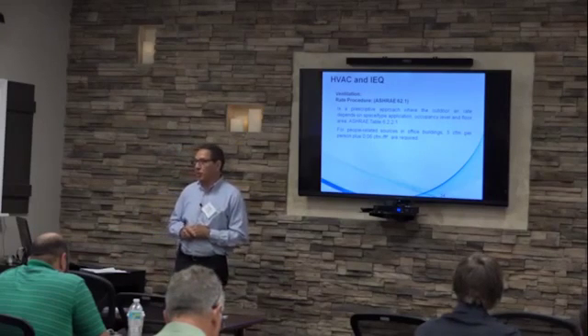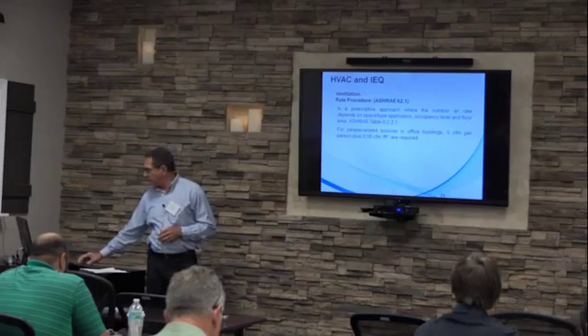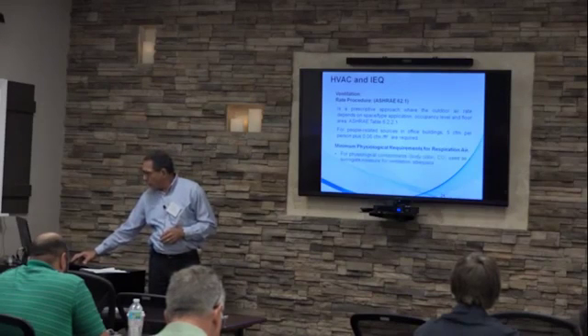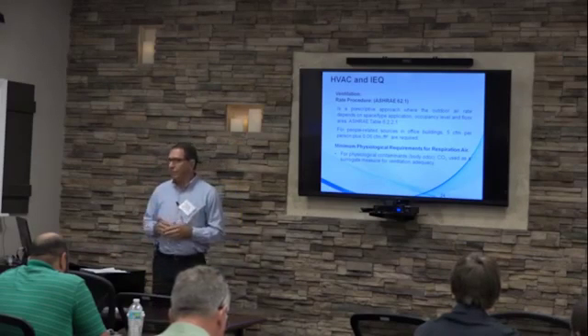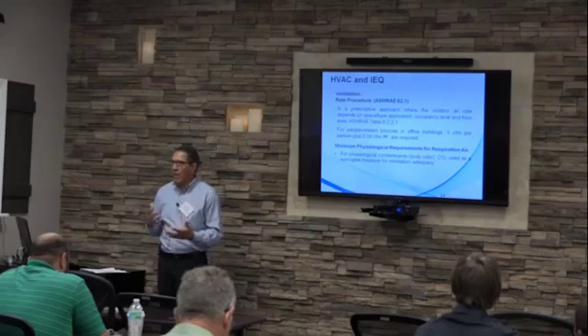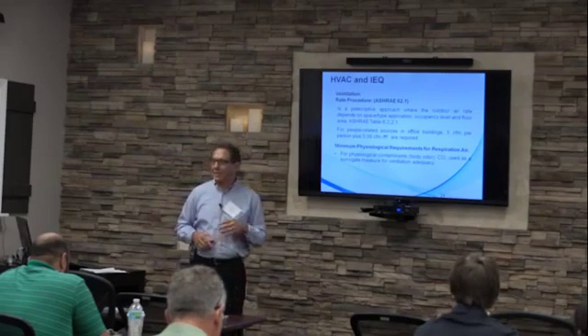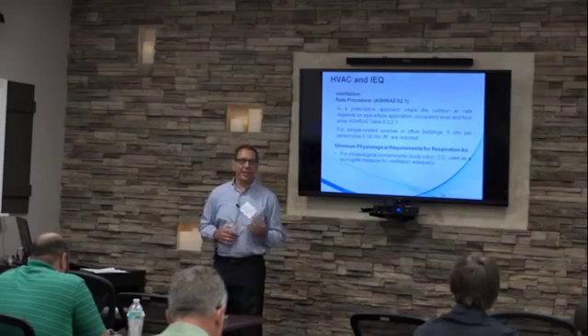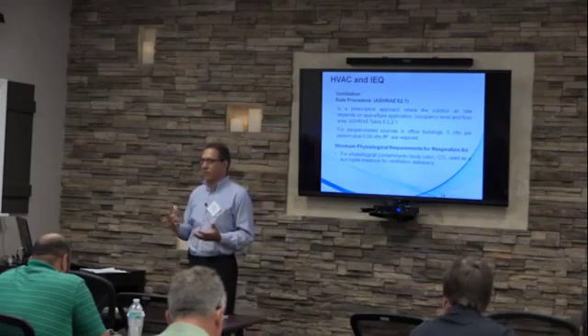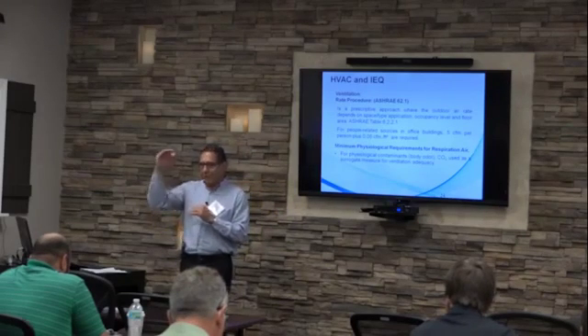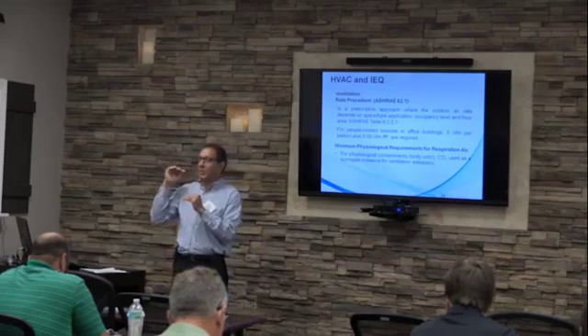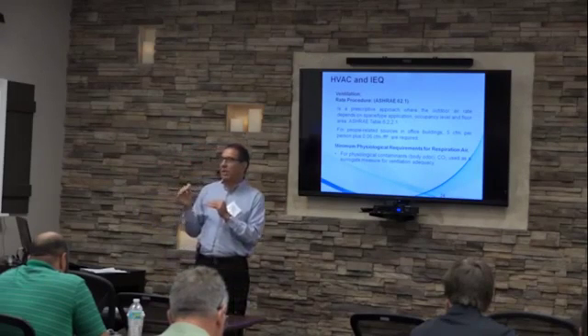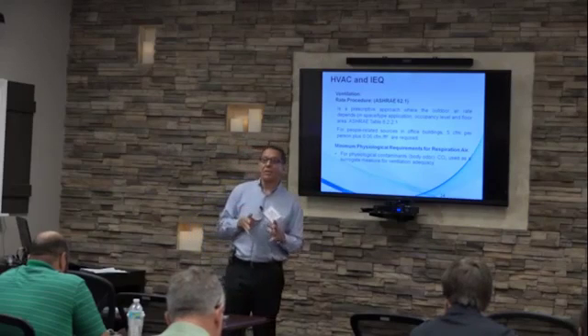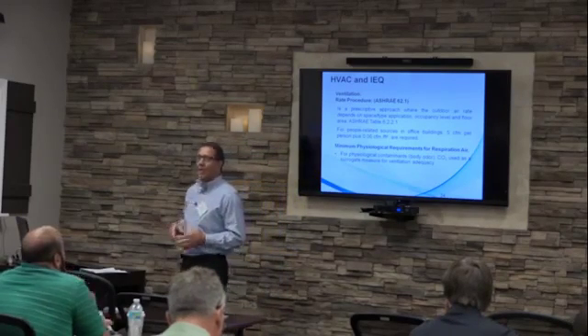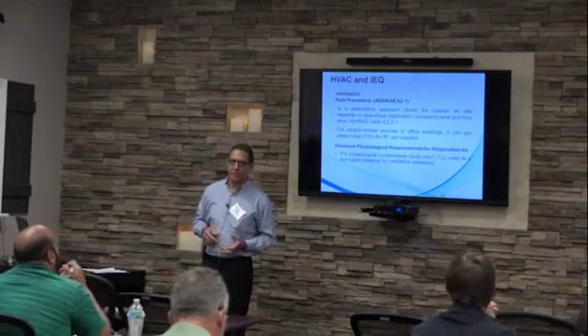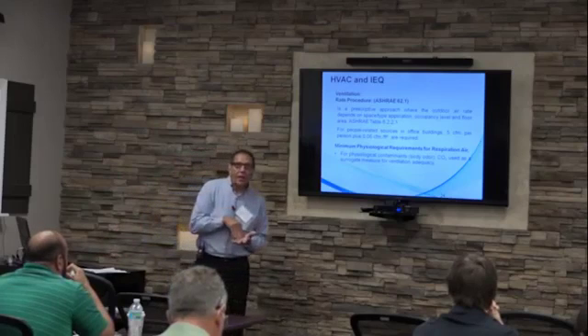For people-related sources in office buildings, they recommend about 5 CFM per person and 0.06 CFM per square foot. For physiological contaminants, body odor, they recommend that carbon dioxide be used as a surrogate measure to assess the adequacy of the ventilation system. We do not study carbon dioxide as a contaminant because in most buildings it is not. Carbon dioxide needs to get to perhaps 13, 14, 15,000 parts per million before it becomes a contaminant. But carbon dioxide in indoor air quality assessments is used to assess or roughly understand the adequacy of the ventilation system.